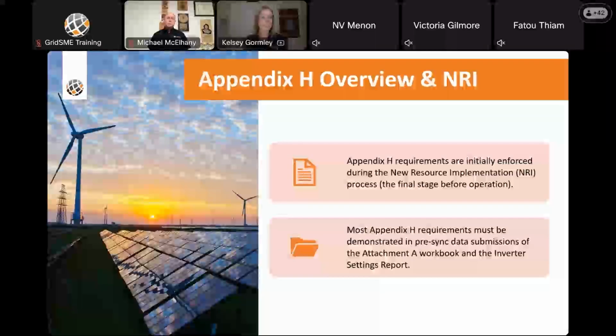And again, my favorite topic is definitions. So sync, the definition of sync in this context is you will be moving from not utilizing grid power to commission your facility to moving into what most people would refer to as the test energy phase. You are using grid power, submitting test energy schedules to CAISO, and you are either putting electrons onto the grid or pulling electrons off the grid if you're a storage facility. So for the purposes of this conversation, pre-sync means you have to have all of this documentation in and accepted by CAISO prior to putting any electrons on the grid or taking them off the grid, if that makes any sense to everybody. So this happens in typically bucket 3 of 6 in the NRI process.